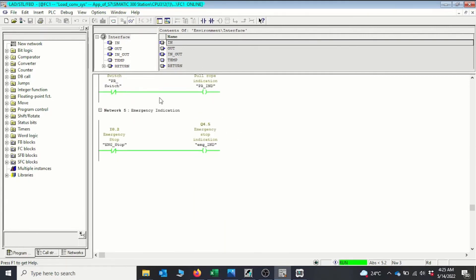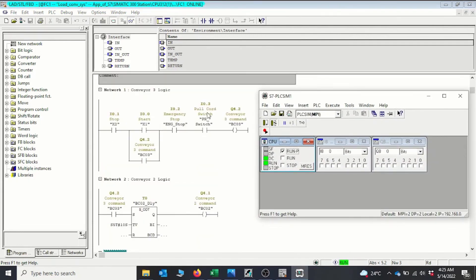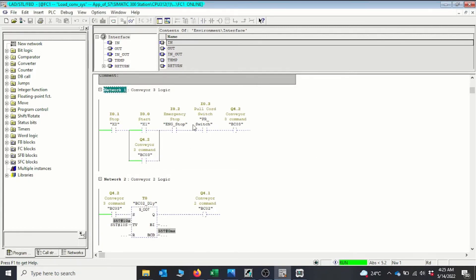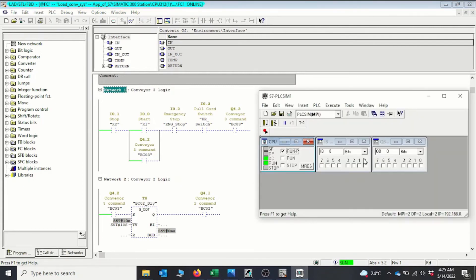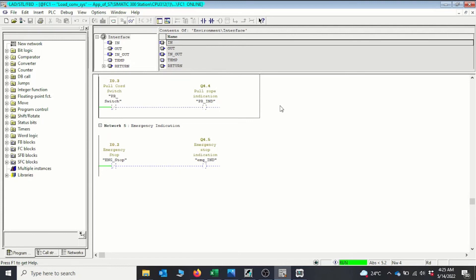We can see the indicators are on because the switches are normally closed on the field. We need to activate them and give them a normal signal before they go off, and then this section will be ready to start the conveyors. So I take I0.2 — it's closed now — and I take I0.3, indicating they are now okay on the field. The lamps are now in off state because they are not in alarm.